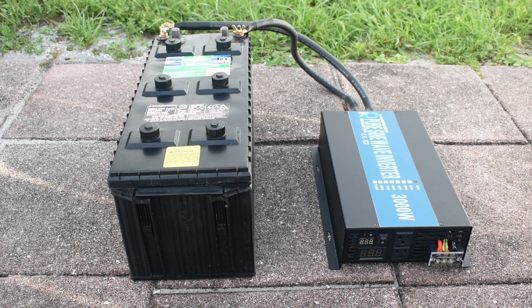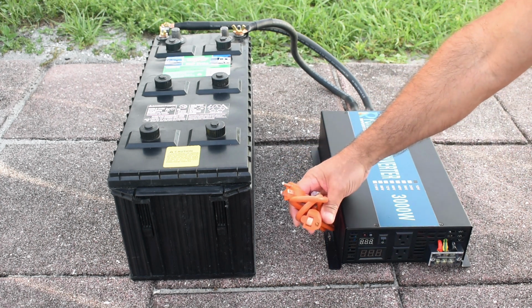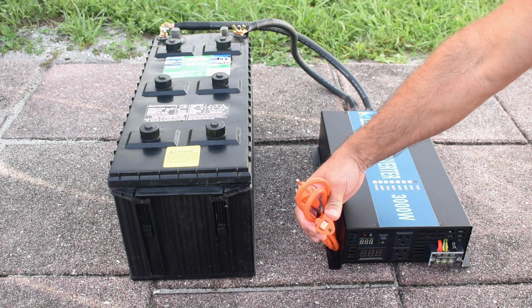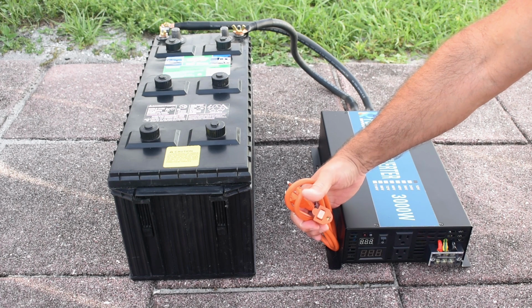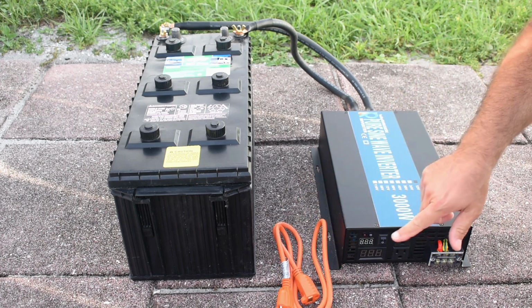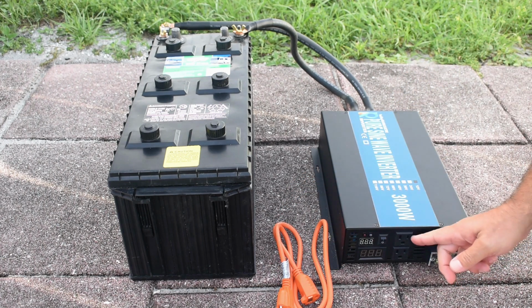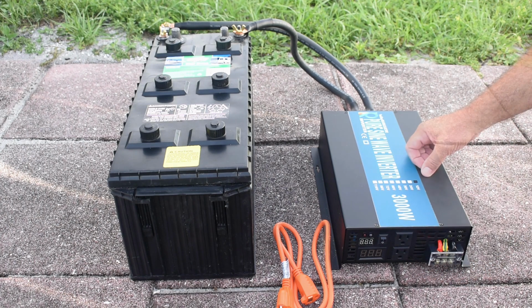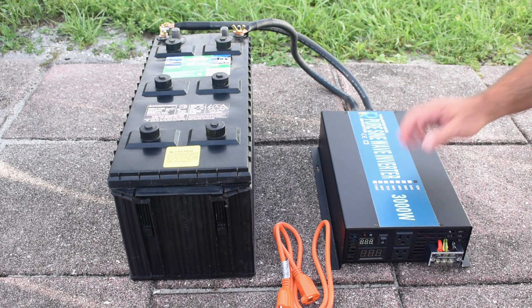We're now going to test protection for AC output short circuit. You can see this extension cord, I have the prong shorted using a copper strip. I'm going to turn this on, then plug it in and see if this turns off. According to the manufacturer, this inverter should not blow up performing this test. I moved to the outdoors just to be safe. Let's give it a try and hopefully it works.